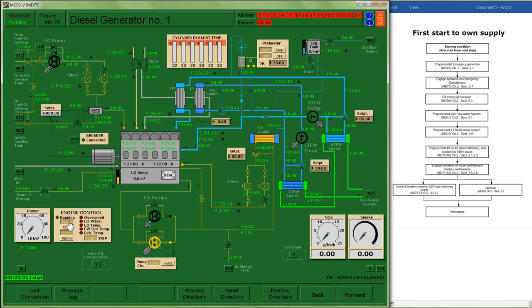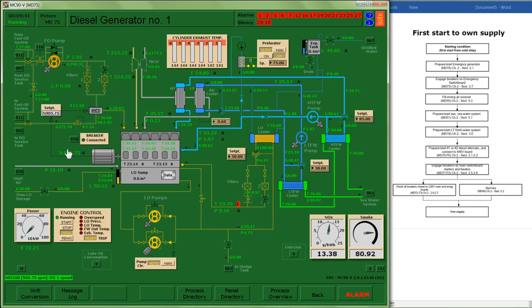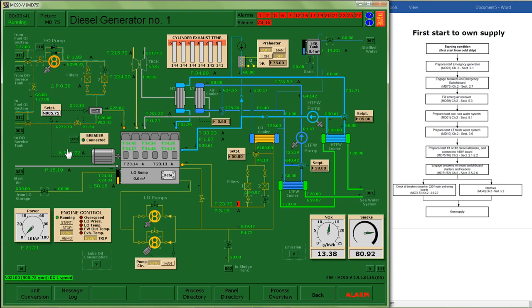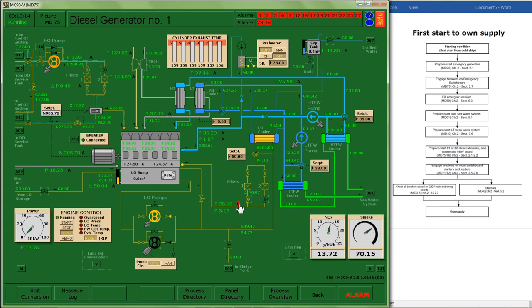My generator normally operates at approximately 900 RPM, and I can see that I have just over 900 RPM. I got an alarm that shows low temperature in my lube oil system, which I can expect because I haven't had any warm-up of my system, so pre-warming. Temperature looks like it's rising, so that should go away. Ideally, I would want hot coolant and hot oil before I start up my engine.